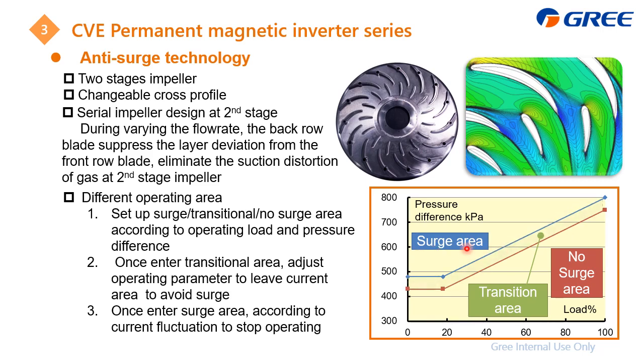As you know, if we enter the surge, it will lead to the current fluctuating a lot and also damage the compressor. It will be very dangerous. So if we enter this transitional zone area, we will adjust the parameter to make it leave, to avoid the surge.